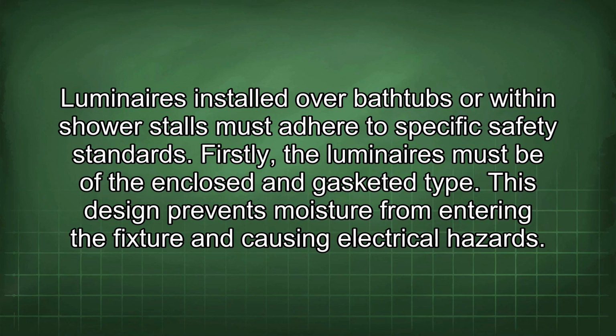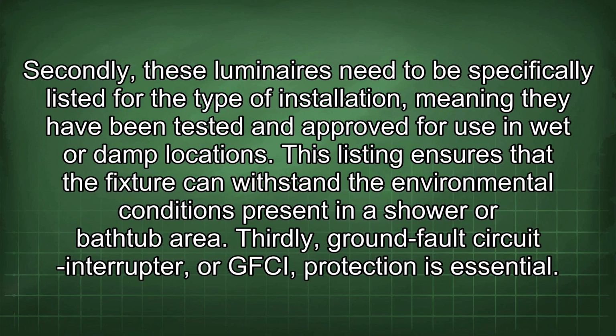Luminaires installed over bathtubs or within shower stalls must adhere to specific safety standards. Firstly, the luminaires must be of the enclosed and gasketed type. This design prevents moisture from entering the fixture and causing electrical hazards. Secondly, these luminaires need to be specifically listed for the type of installation, meaning they have been tested and approved for use in wet or damp locations. This listing ensures that the fixture can withstand the environmental conditions present in the shower or bathtub area.